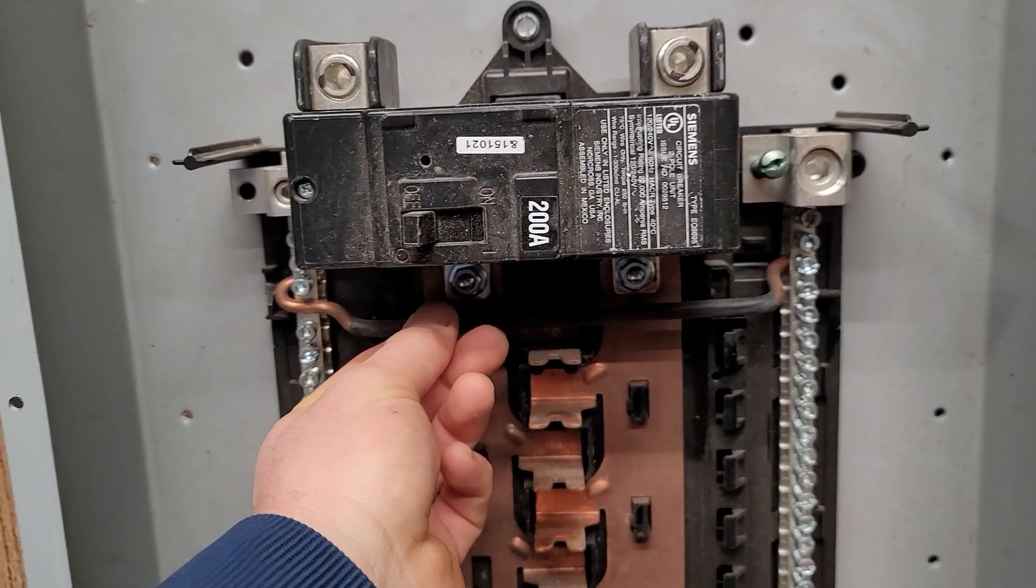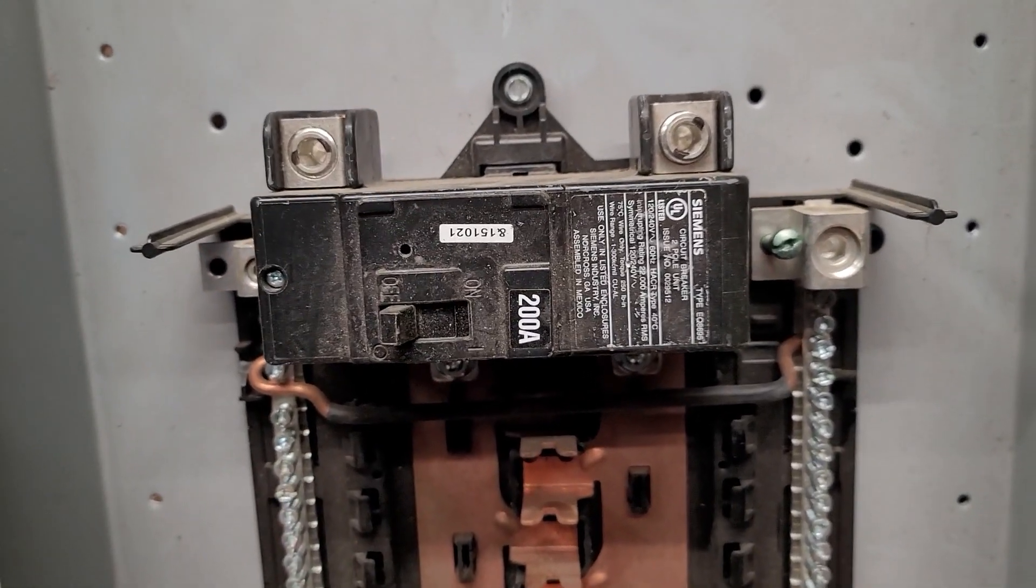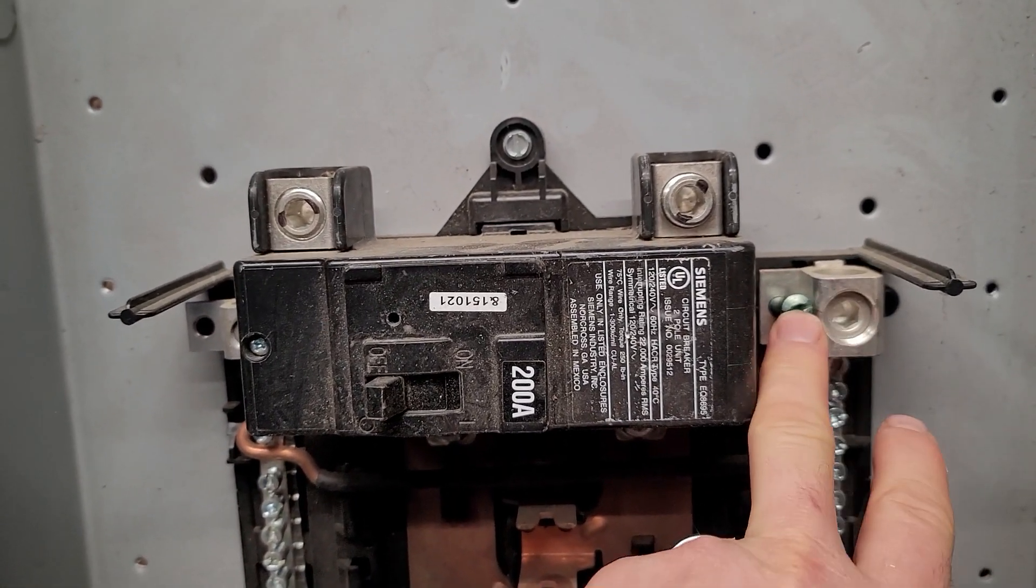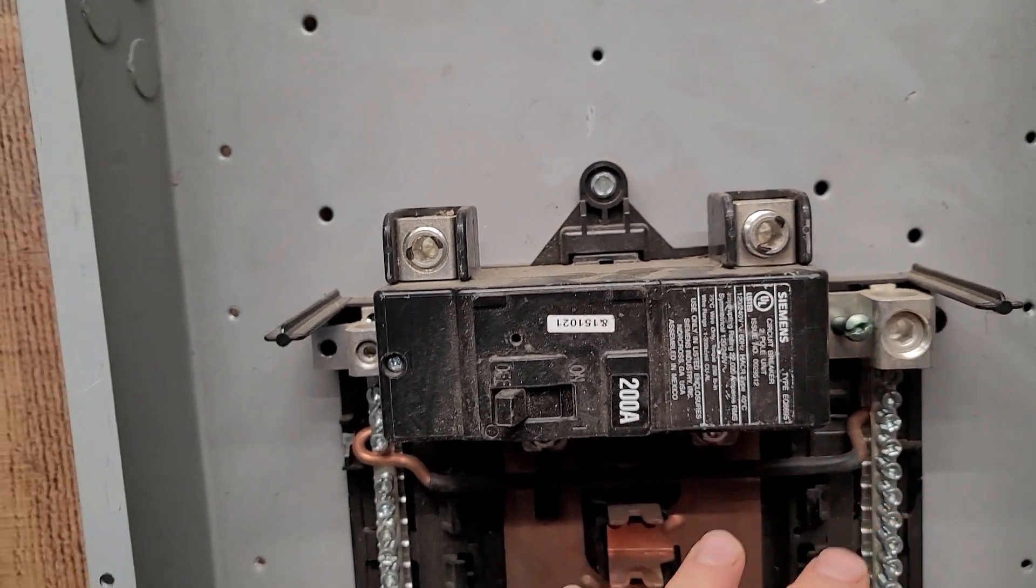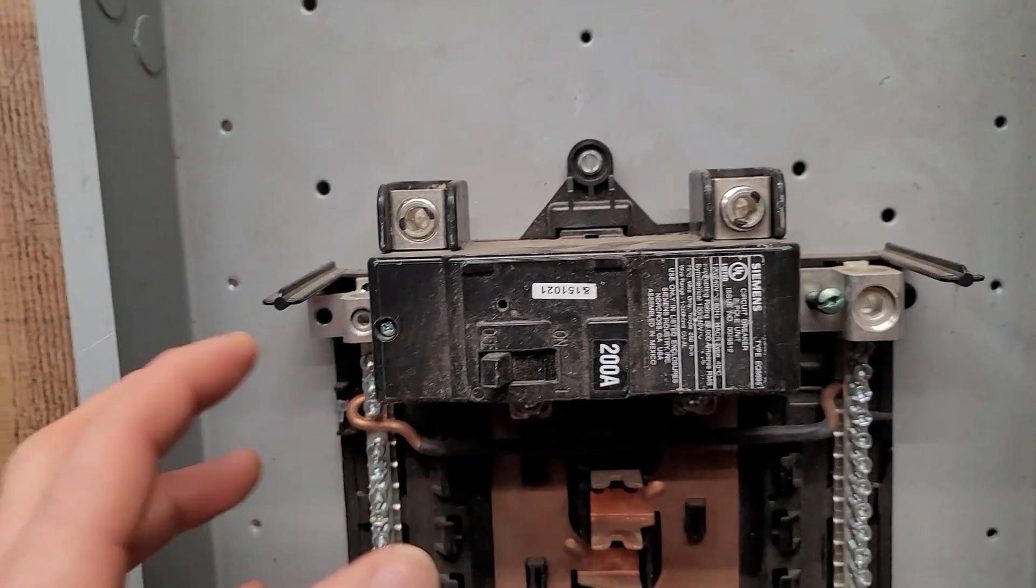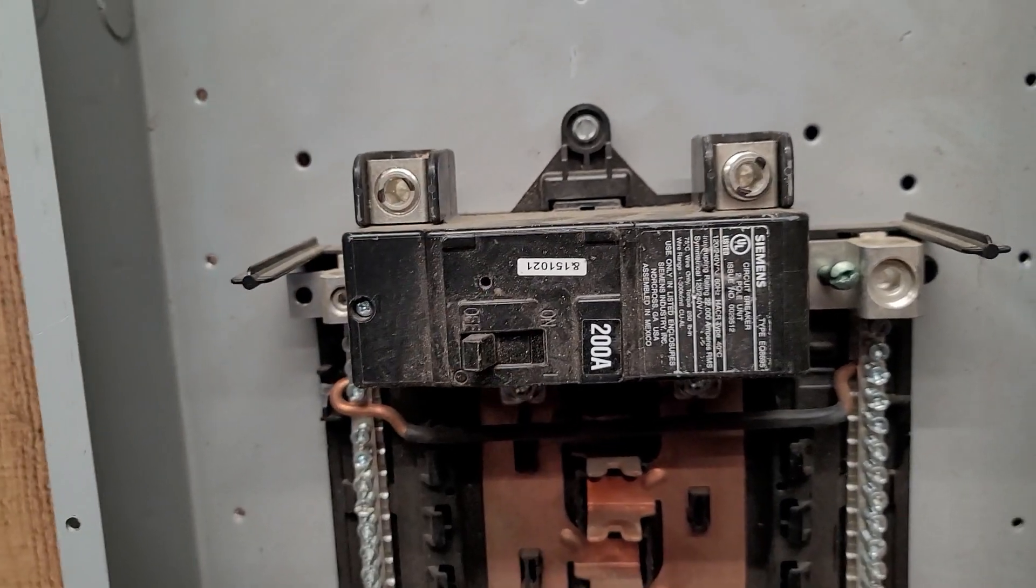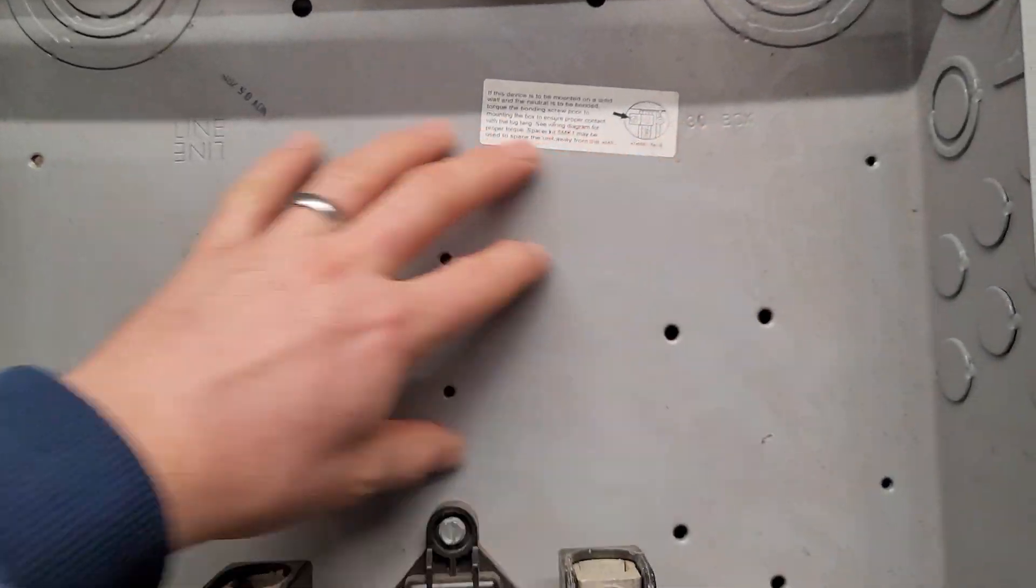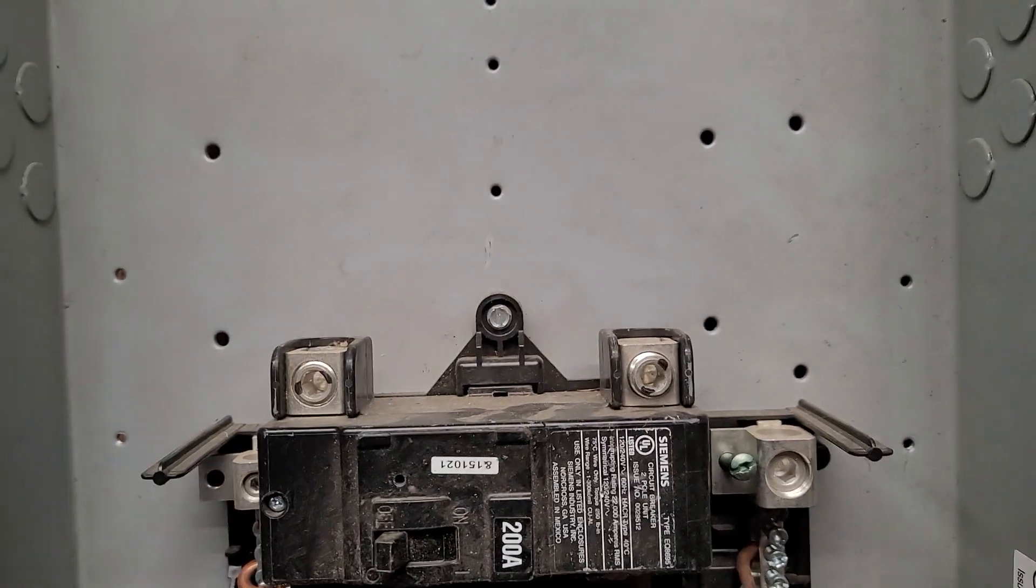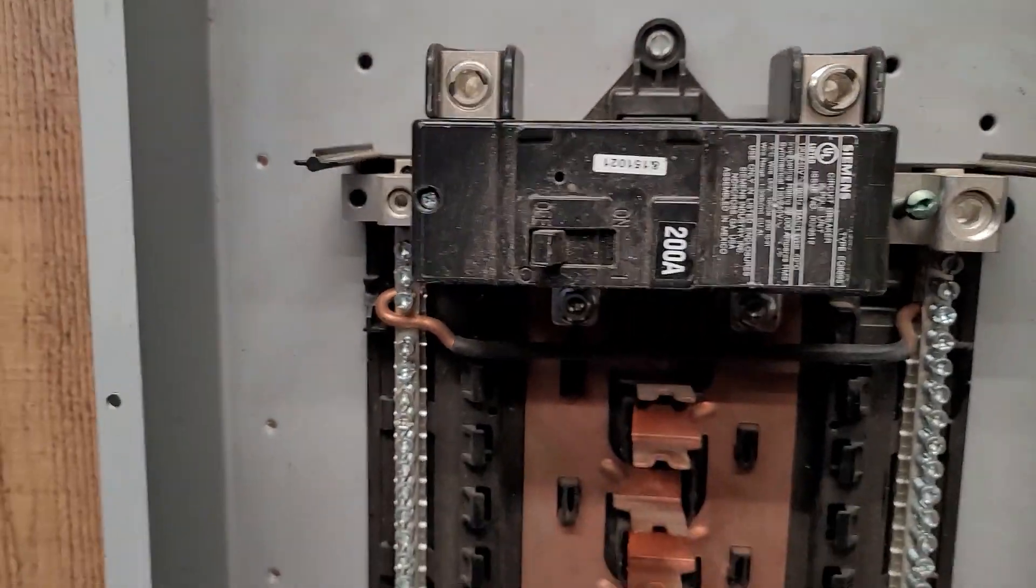So today I want to talk about this little bar right here. If this were the first point of disconnect we would drive our main bonding jumper screw in. We'd make sure it was tight and that would connect our neutrals to our grounds here at the system. So whether we put extra ground bars up here everything would be bonded including the frame of the panel, the can itself.